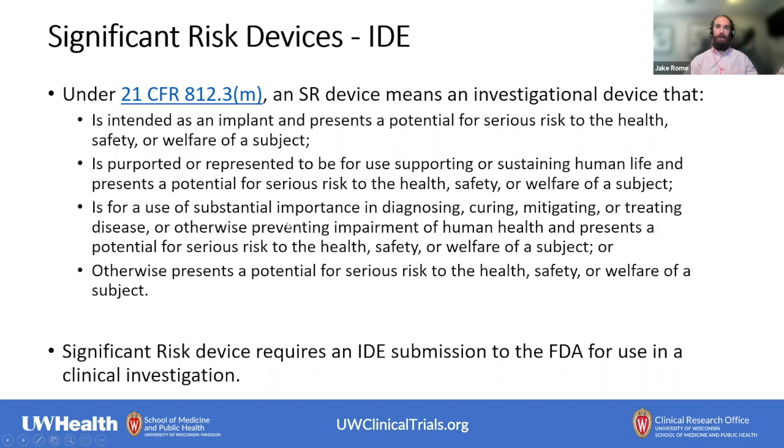And as part of the use of that device, you may be doing something like a lumbar puncture. And so you're pulling spinal fluids to see whether or not your use of the device is showing up as being effective based on what's happening in the spinal fluid. In that case, the FDA would come out and say that that is a significant risk device investigation, because although the device that you're using might not present significant risk, you are presenting subjects with significant risk through that lumbar puncture, and therefore you would be required to submit an IDE to the FDA to get approval to use the device in that type of research study.